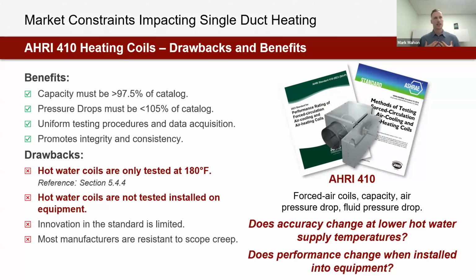I will say, as a voting member of this standard, innovation is pretty limited. There's a ton of manufacturers who have representatives on this standard, and it's hard to get punctuation changed, let alone full new versions of a test added in, at least with pace. And I would say most manufacturers look at the testing cost and scope and really don't want to see that scope creep over time. So the questions I would ask of the market, the questions I would flag to the standard committee, is: are people's accuracies for hot water coils changing at lower water supply temperatures? And what happens when that water coil is actually installed into equipment? What happens if it's right downstream of a damper that's almost fully shut? What changes? And so those are the questions I think consulting engineers need to be concerned about too. And those are the questions. I'll dangle this: we're going to answer those later in the presentation.